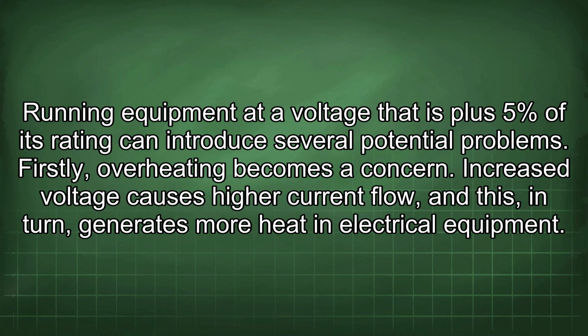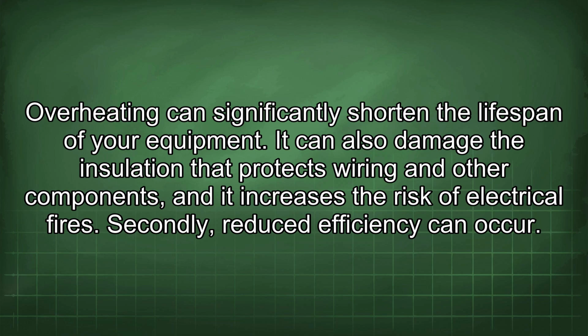Running equipment at a voltage that is plus 5% of its rating can introduce several potential problems. Firstly, overheating becomes a concern. Increased voltage causes higher current flow, and this, in turn, generates more heat in electrical equipment. Overheating can significantly shorten the lifespan of your equipment. It can also damage the insulation that protects wiring and other components, and it increases the risk of electrical fires.